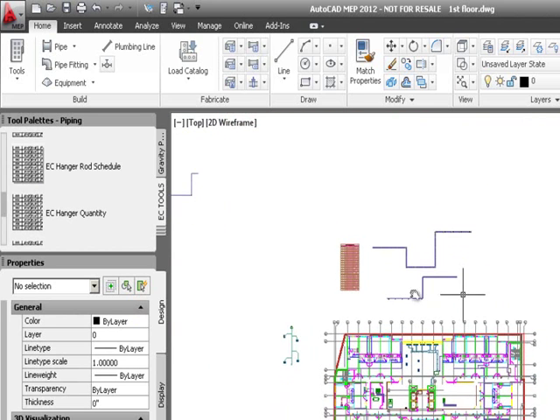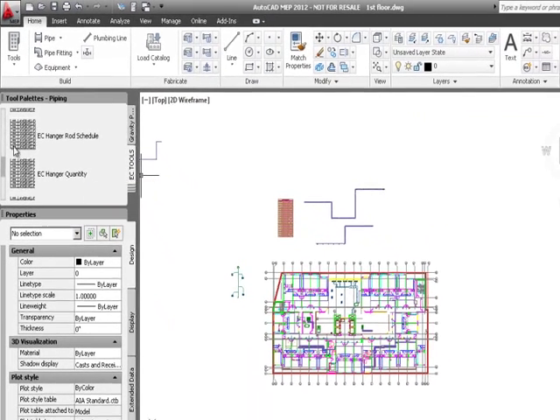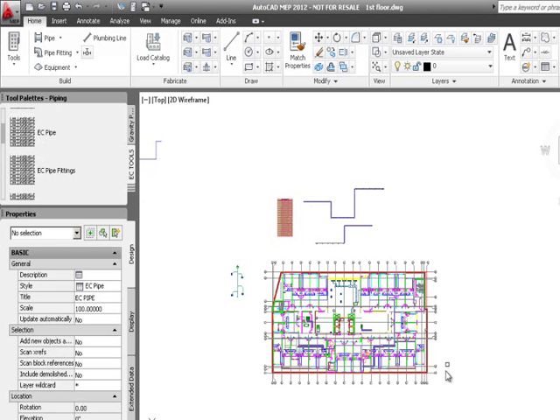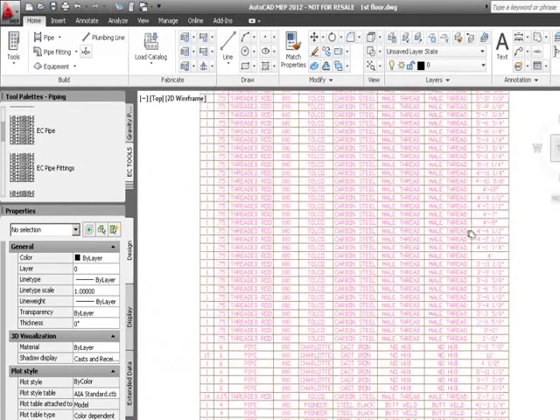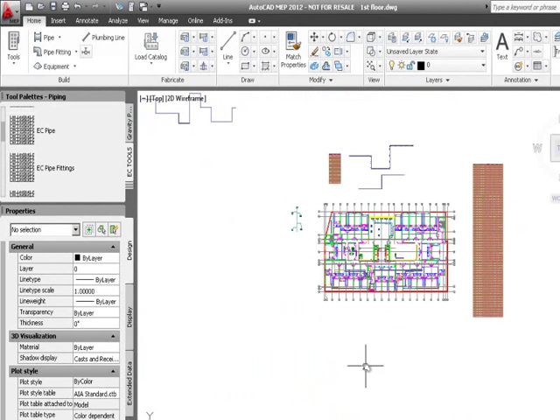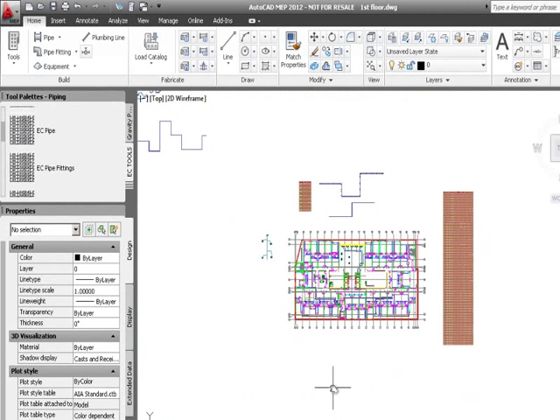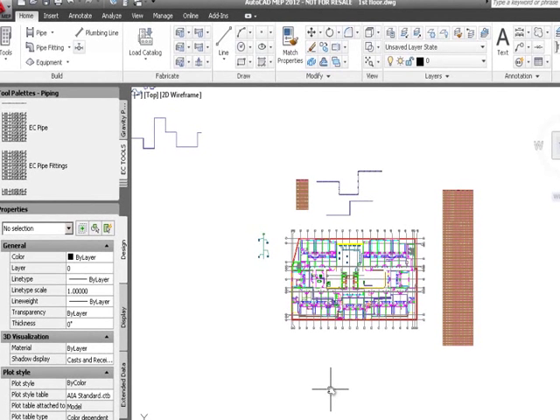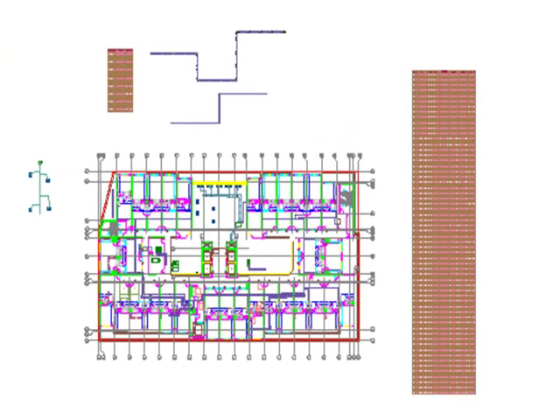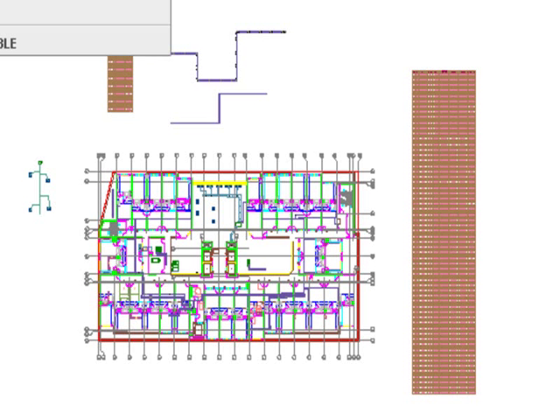I can get any schedule out of the drawing that I choose, and all are customizable. Selecting the entire drawing gives a schedule of every cut length of every piece of pipe. To recap: we can bring in custom parts from any manufacturer right into AutoCAD MEP where they behave exactly the same as all MEP parts. We can convert existing MEP content to real manufacturer content, create schedules and spool drawings, insert hangers, and export the file to Trimble to pick up points for the hanger so GPS can locate them.